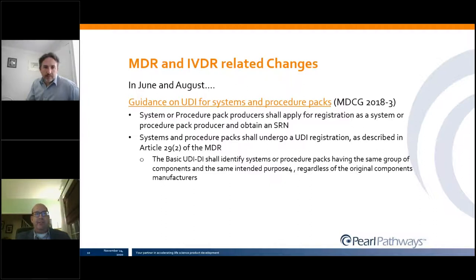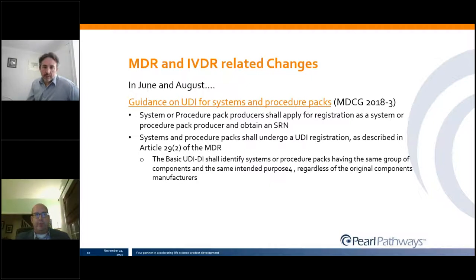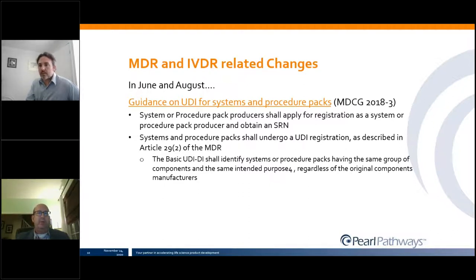In June and August, a couple of guidances came out. One relates to UDI for systems and procedural packs, providing clarification on how to apply for registration of a system or pack of products and obtain the SRN number. They must undergo UDI registration as described in Article 29, and the UDI would cover the same group of components and same intended purpose, regardless of the original component manufacturer's UDI.